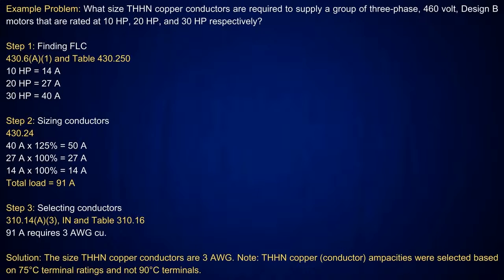Now, here's one where you've got multiple motors. Everything's still the same. I've got 460-volt 3-phase motors here, okay? I've got a 10 horsepower, 20 horsepower, and 30 horsepower. Well, I already know the 30 is going to be the largest. But I go to table 430.250, get all my amperages. So a 10 horsepower is good for 14 amps, 20 horsepower is 27 amps, 30 horsepower is 40 amps.